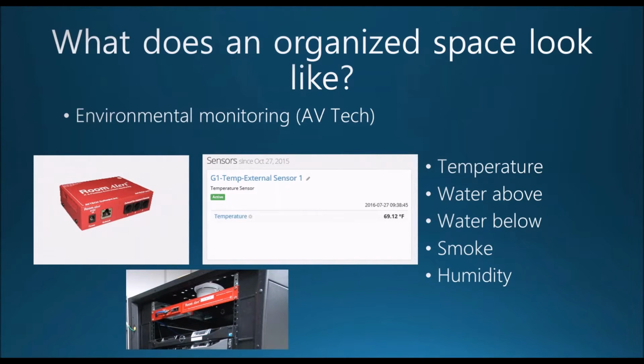That's also great for water issues, like a sprinkler head. On the top of the rack there's a rope that goes around the top, constantly monitoring for wetness. If the sprinkler head blows, that cord gets wet, and it tells the system there's water here, so it automatically shuts down the servers before they get wet enough to cause electrical issues.